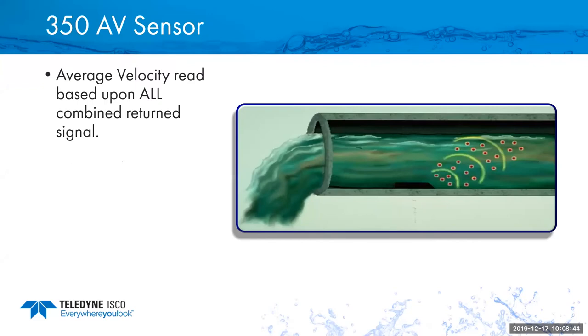The 350 area velocity sensor is a sensor that's mounted into the flow, typically towards the bottom of the channel or bottom of the pipe, that uses the pressure of the water to measure the depth and then fires an ultrasonic signal into the flow and returns an average velocity based off the Doppler shift of the particles in the water.